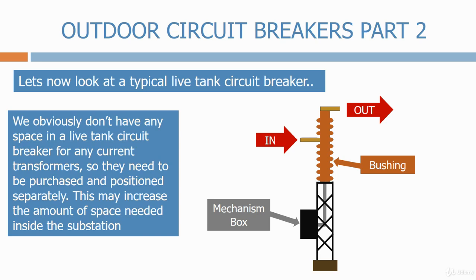We obviously don't have any space in a live tank circuit breaker for any current transformers, so they need to be purchased and positioned separately. This may increase the amount of space needed inside the substation.